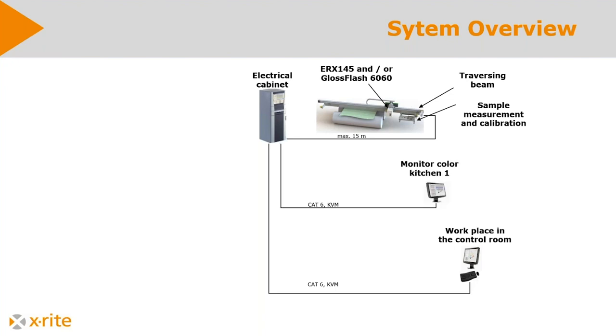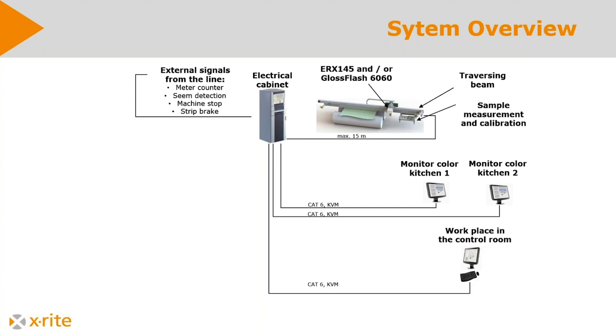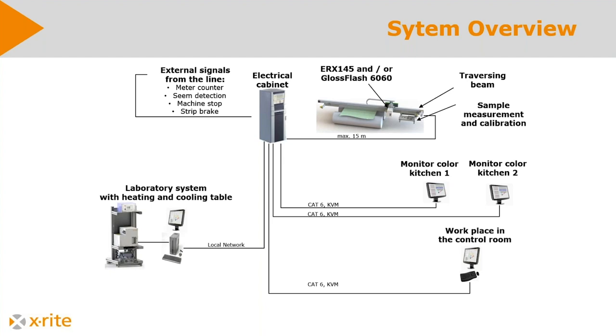Very often people in the color kitchen want to see the color as well because they need to know how to prepare the color, how to adjust the nip press, whatever. So they have a monitor over there, and if you have coatings from two sides, of course, we can have two monitors for each color kitchen. We have external signals. Very important is, for example, the seam detection. If there is a seam, we move the instrument out so that the coil seam can pass by, and then we start again. Meter counter is also very interesting. We have many different signals here. And what is very important, we can have an instrument in the laboratory to measure the standards. I'll show you later why this could be very important.